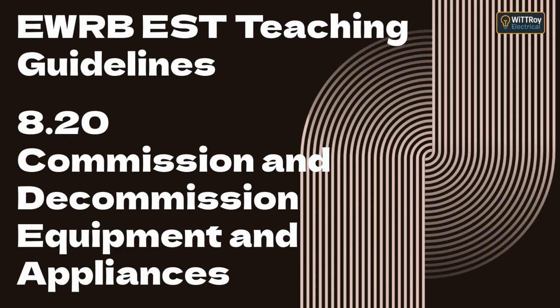Then perform the prove, test, prove sequence. 1. Prove your tester on a known live source. 2. Test the circuit to confirm it's de-energized. 3. Prove the tester again to confirm it's working. Only when the test confirms 0 volts may you proceed.